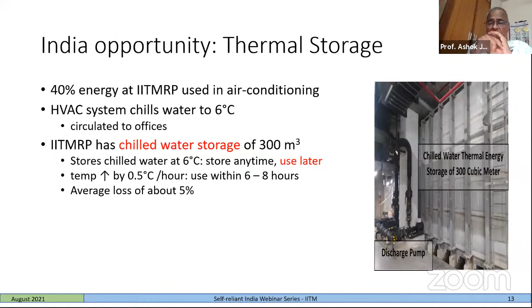It's a storage, and this cost is much, much less. I will in a minute start talking about IIT Madras Research Park, where we have a chilled water storage of 300 cubic meters, which is effectively 17,470 megajoules, and with a COP of 2 we have a 2.5 megawatt hour storage. Remember, this storage costs much less than lithium-ion storage.